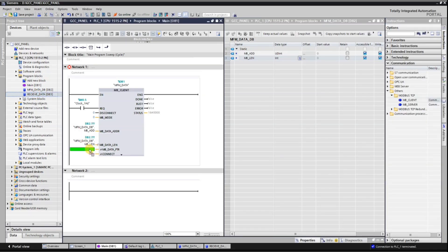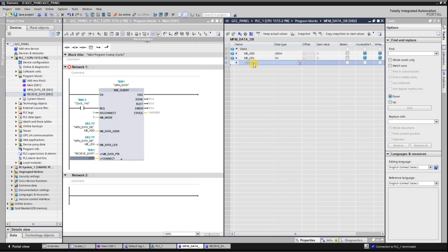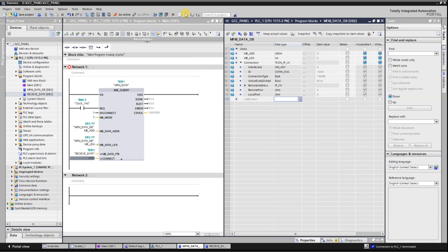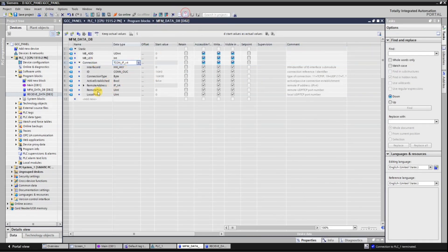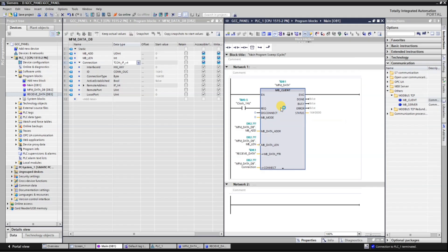Now you can drag and drop the DB where you want to receive data from the multifunction meter and make a connection where we write the properties of the server or multifunction meter. In data type you type TCON_IP_V4. Here you can see we have many options like interface ID, connection type, active established, remote address, local port, and remote port.